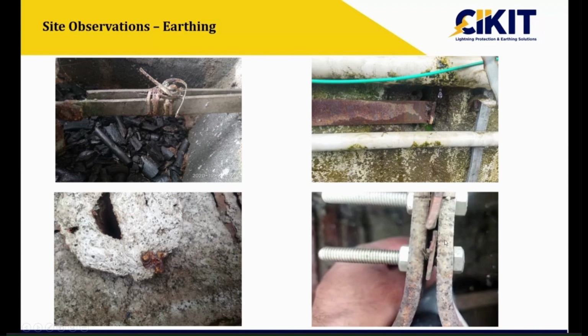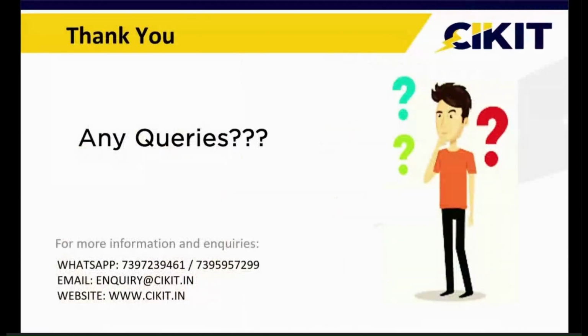In this, there is an air gap between the clamp and the conductor. With the air gap, the connection is not proper. That is what we mentioned. The terminal connection should be proper to avoid these air gaps and loose connections.